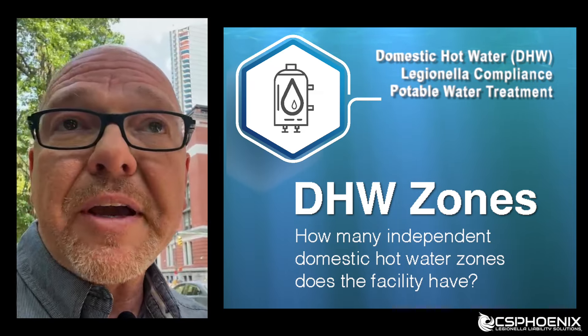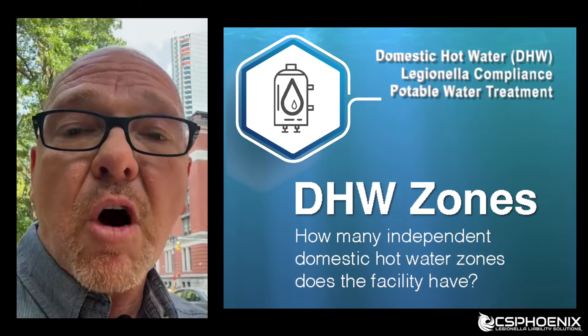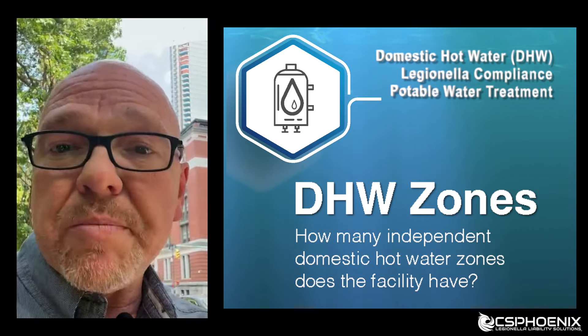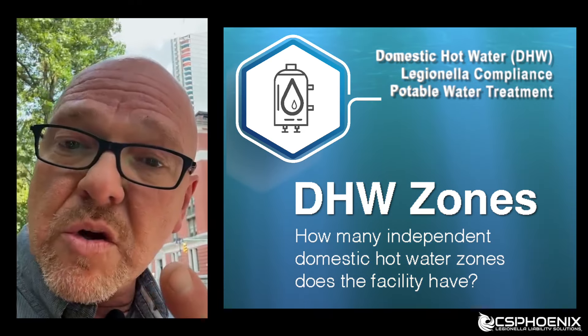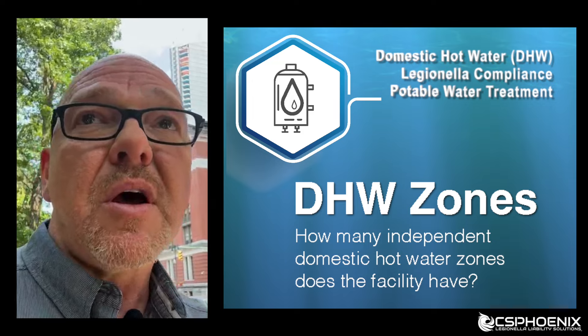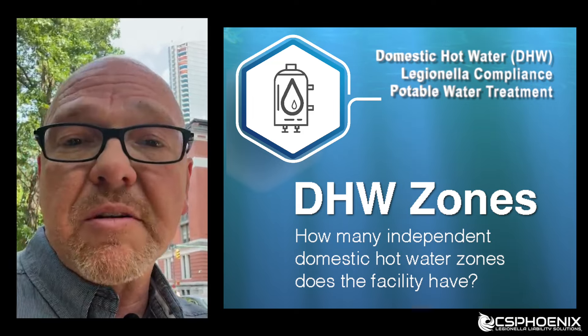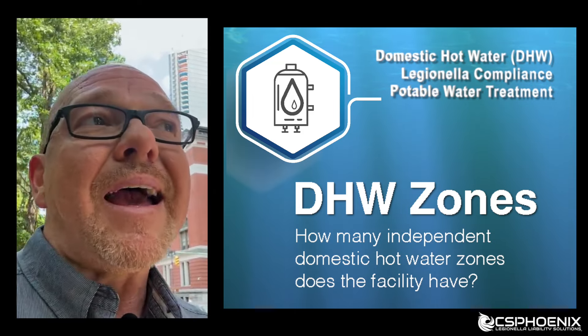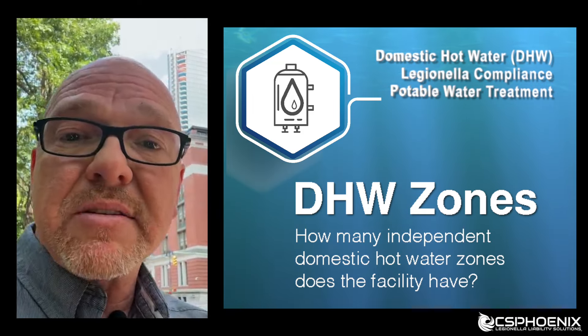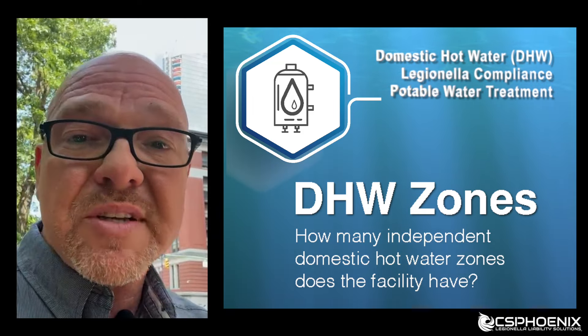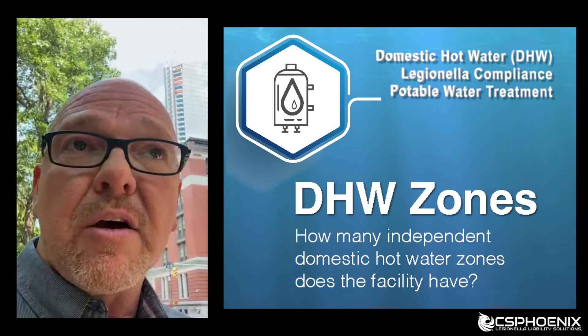You might have two hot water heaters on a common loop — that would be just one zone. If you have multiple hot water heaters that go out into the building and return separately into separate zones, never re-blending back together, that would be a dual zone.